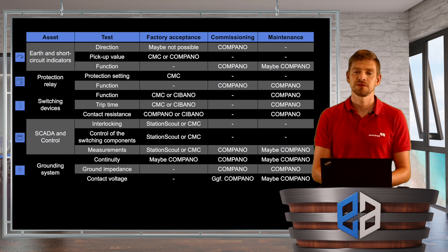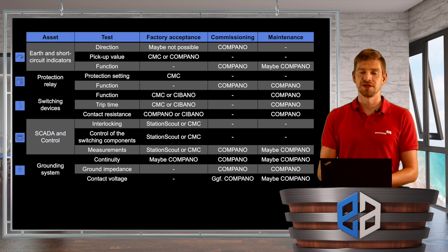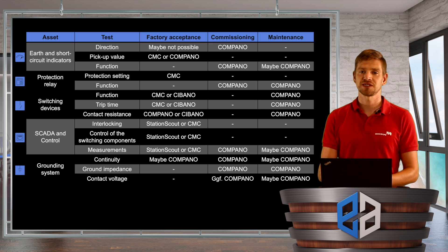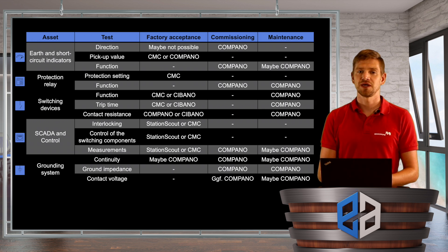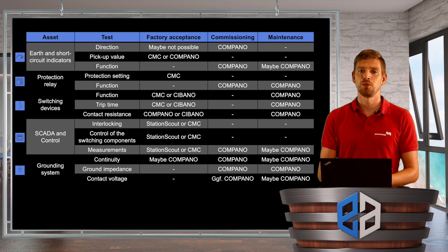The same applies for the switching devices — with the CMC or CIBANO you can focus on function and trip time or contact resistance. In maintenance you can perform simple checks with the Compano. For SCADA, depending on the standard used — for example IEC 61850 — you can use the Station Scout or the CMC for comprehensive testing, and simpler devices for commissioning and maintenance. For the grounding system where continuity is important, you can use the Compano for contact resistance measurement, or even perform ground impedance or contact voltage tests. In summary, for the factory acceptance test you go into more detail with comprehensive testing devices, while for commissioning or maintenance on site a single-phase device is often sufficient.